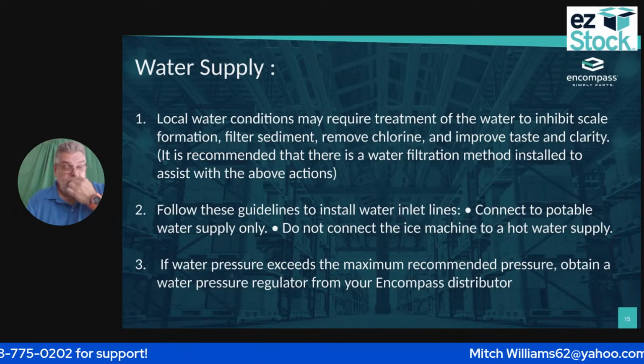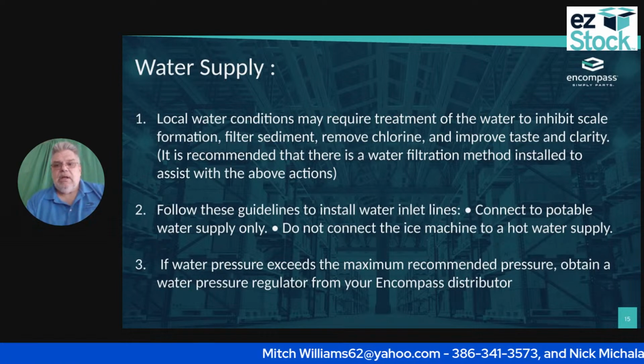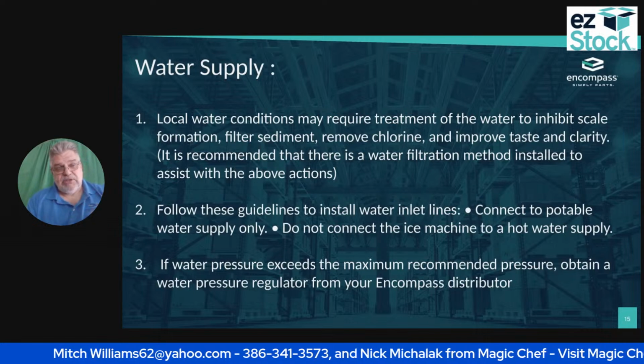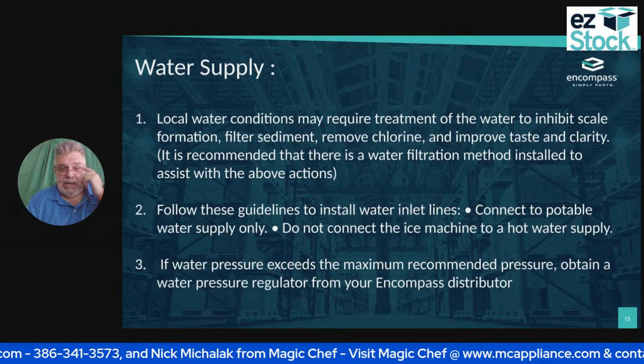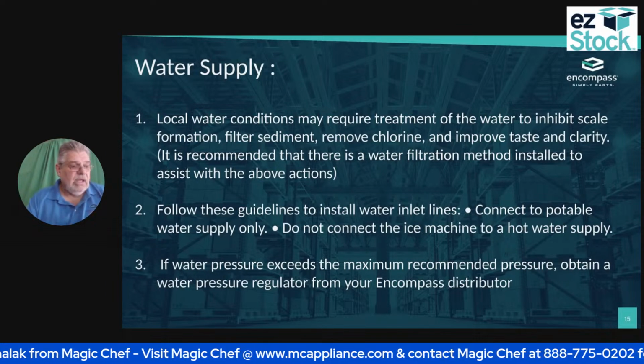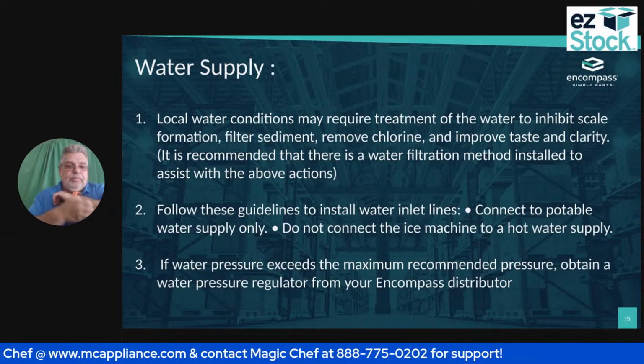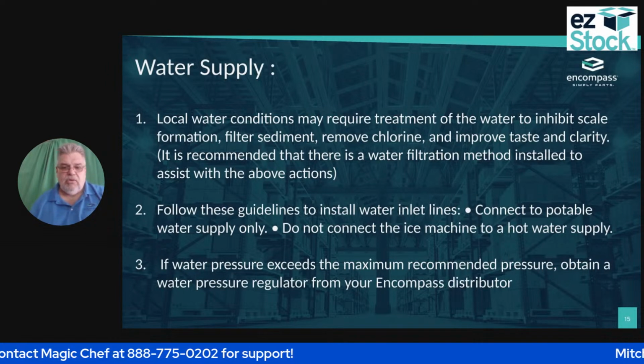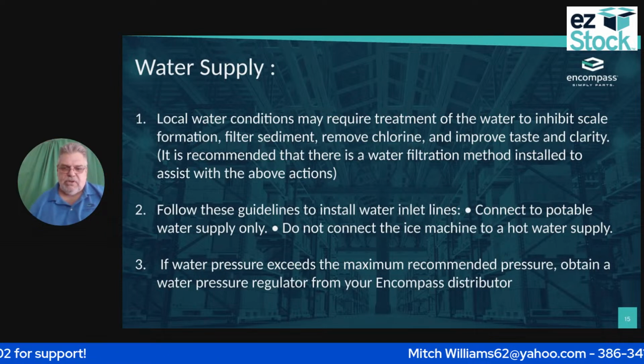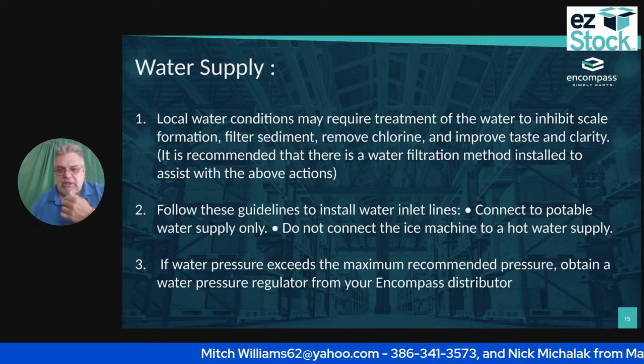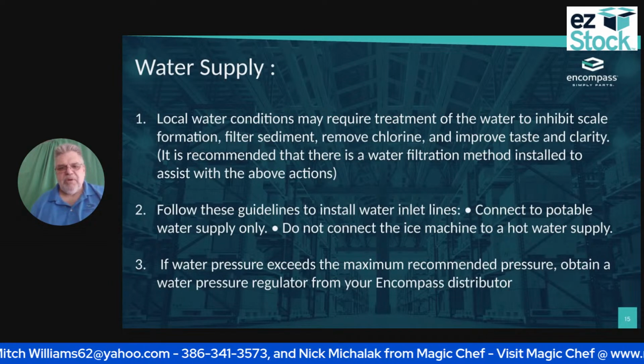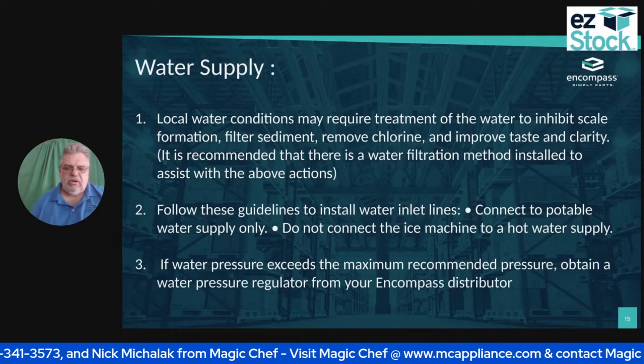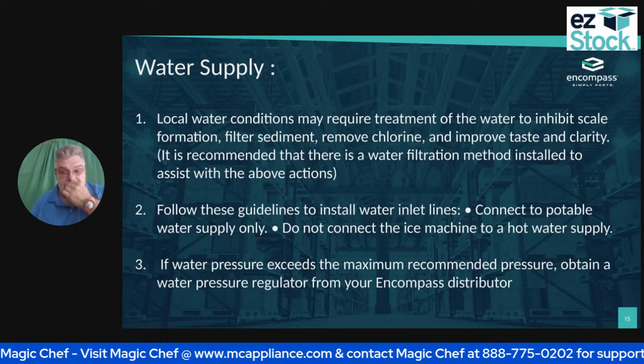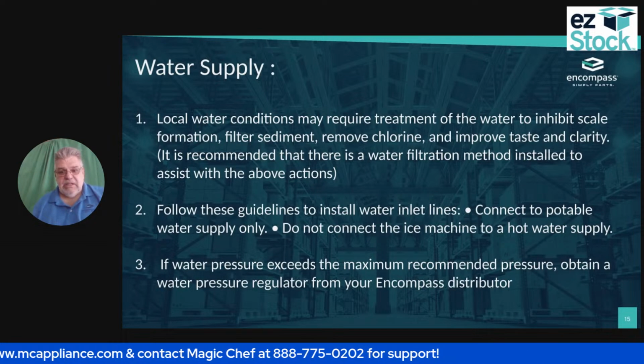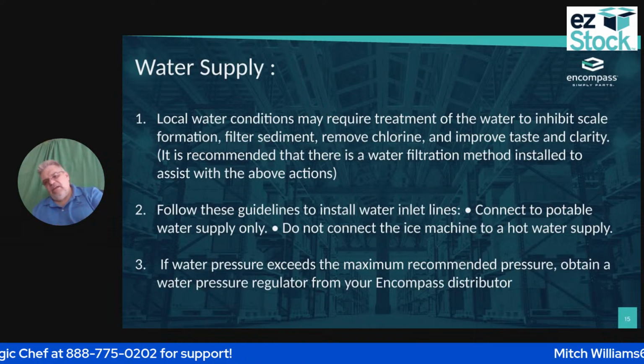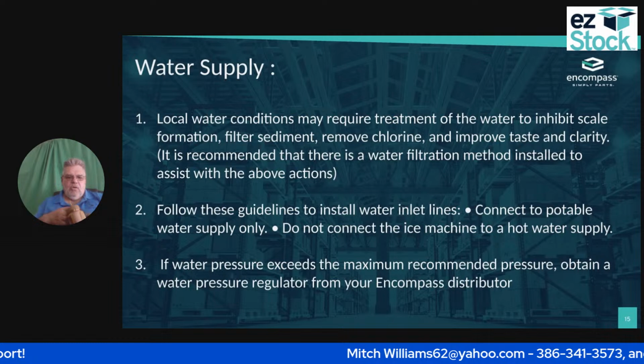If I get the call and it's a year old, one of the things I need to check is whether the water filter has been changed, because if it has not been changed, I guarantee you it's no good, and I'm going to have to change it, and that's part of my problem. Follow the guidelines to install the water inlet lines. Connect to a potable water source only. Do not connect the ice machine to the hot water supply. It goes without saying, but I have walked in and found an ice machine on a hot water supply. We weren't the ones who installed it, and we ended up sealing that valve off and putting it on the cold water side.